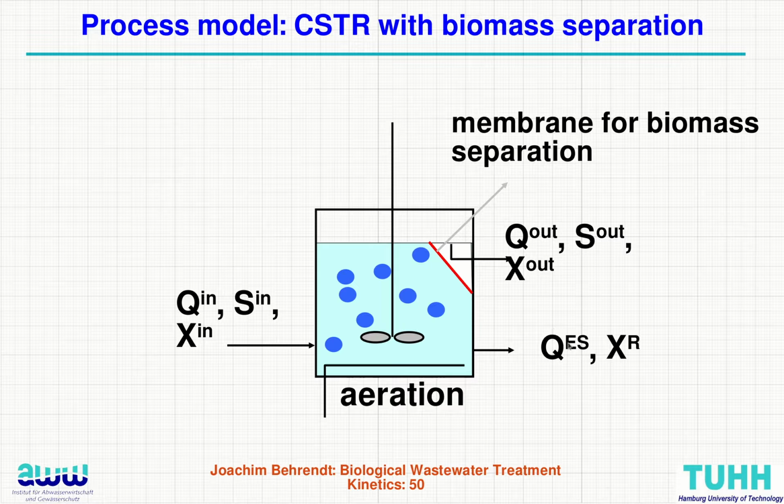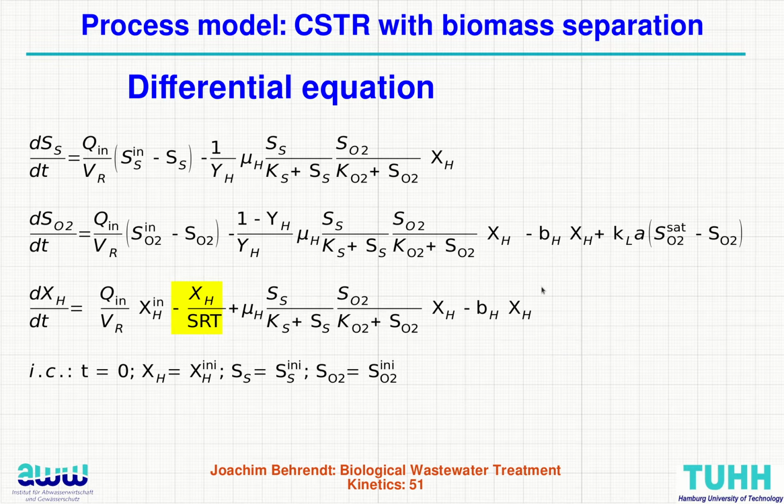But there we are using a smaller amount, and there we have control over the sludge removal rate. The concentration of S is here the same as after the membrane, because this is not changed. And the sum of Q out and QES should be Q in as well. And for this we are doing the mass balance as well, and there we see we have the same.